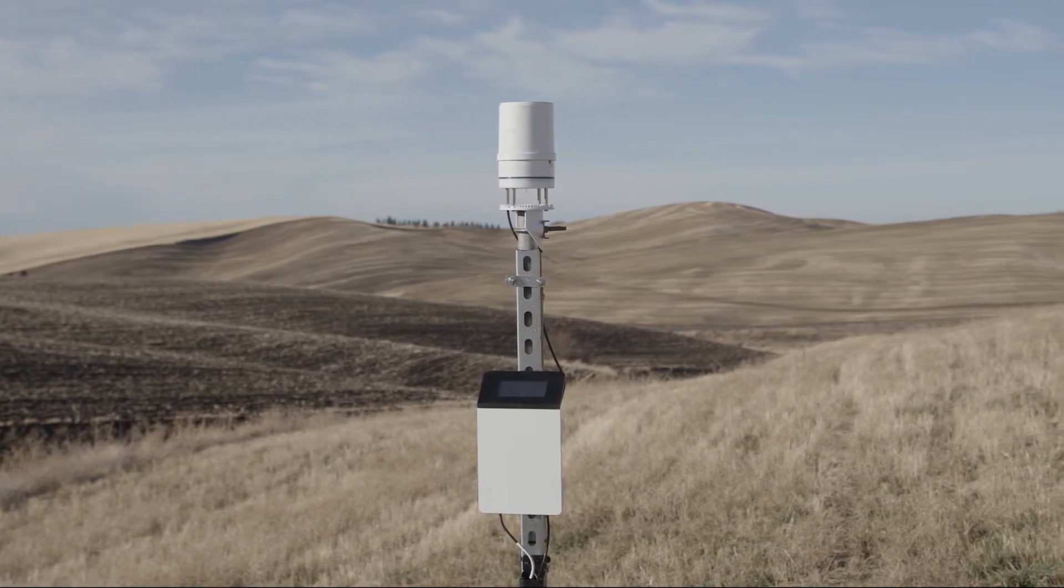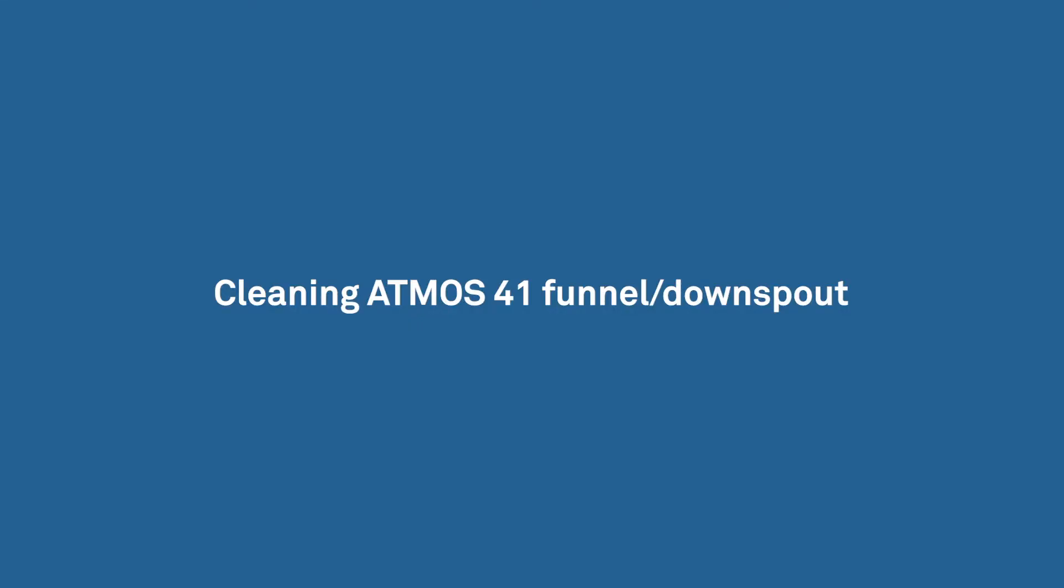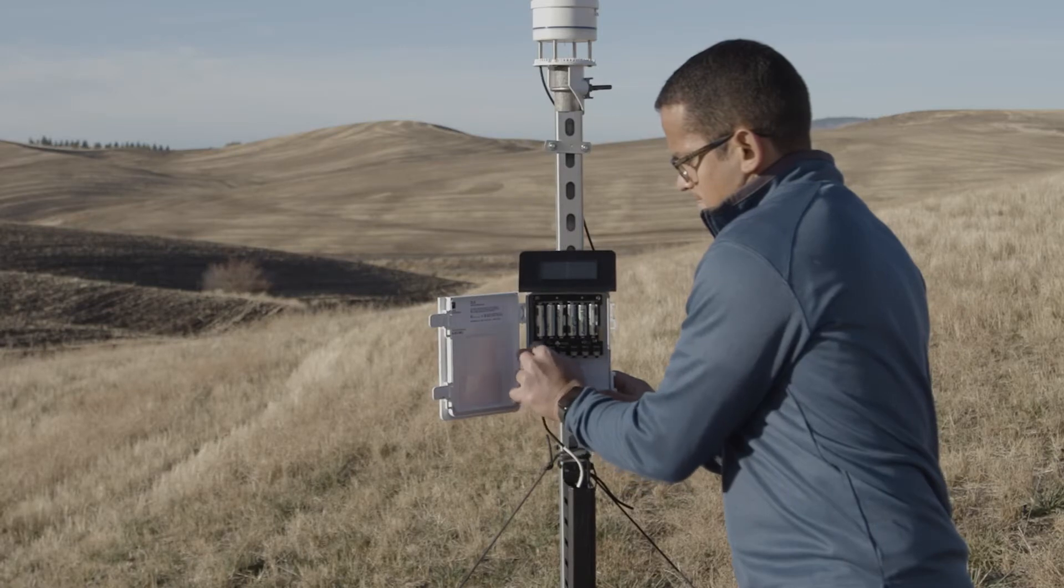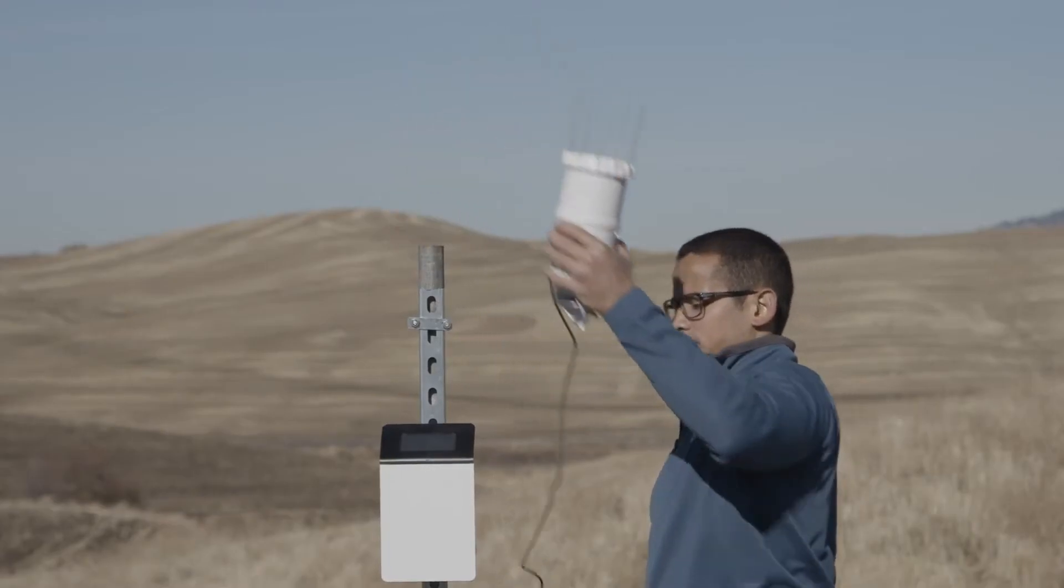For example, the pyranometer needs more frequent checking. To clean the Atmos 41 funnel and downspout, disconnect the Atmos 41 from the data logger. Remove the Atmos 41 from the mounting post.